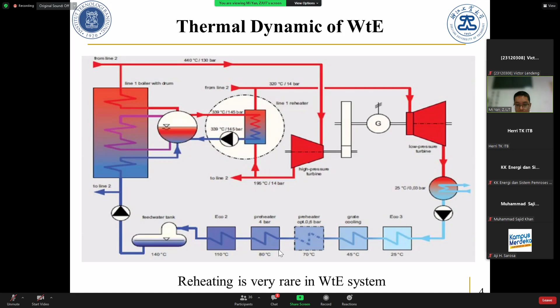For the efficiency of WTE, many participants are very concerned about how much the efficiency of waste to energy is - that means for 1 ton, how much electricity can be produced. Actually it mainly depends on the steam turbine, what's the temperature and what's the pressure of your steam turbine. So with increases of temperature and pressure, the electricity production efficiency will improve. You can see here, if just middle temperature, middle pressure, roughly 20%, then maximum can be up to 30%.